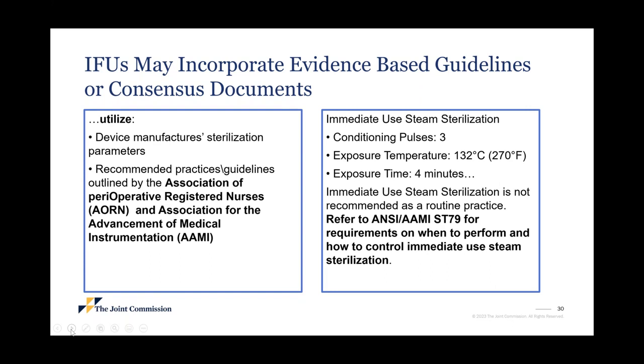The one on the right is much more specific. It says for immediate use steam sterilization, you need a three pulse pre-vacuum system. You need to be sterilizing at 270 degrees for 4 minutes. And by the way, they say immediate use steam sterilization is not recommended as a routine practice. Please refer to AAMI ST79 for requirements on when to perform and how to control immediate use steam sterilization.